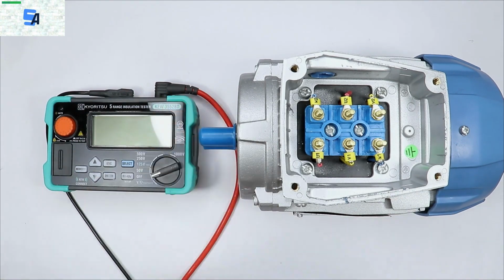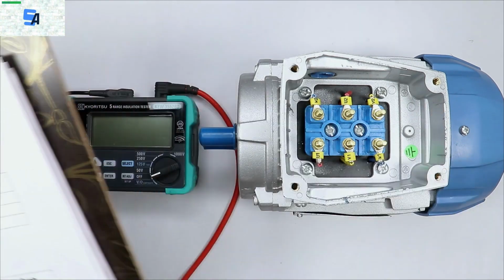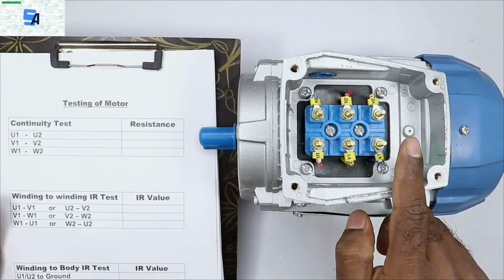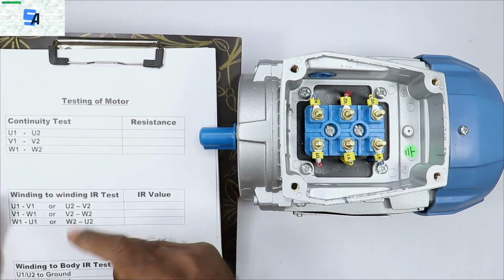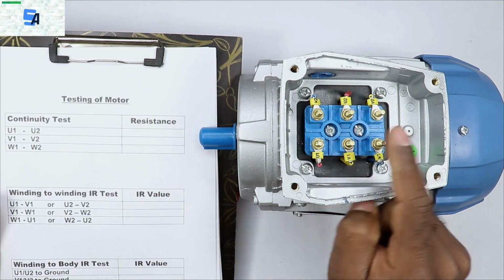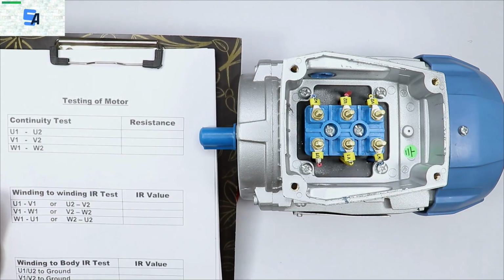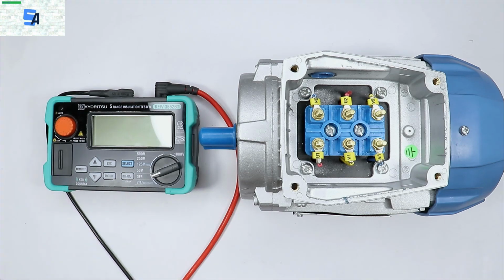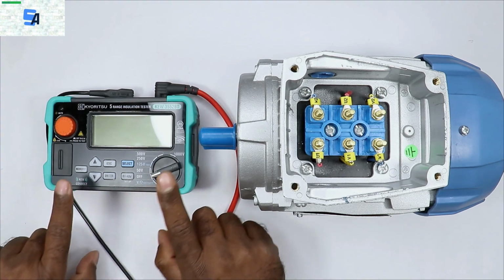Among these, the first way is the winding of the motor. What is the resistance of this winding? We have to measure this. It means we have to do a continuity test of the motor winding. For the continuity test, if you want, you can use a multimeter or you can use an insulation tester also. So I am explaining testing through the insulation tester.